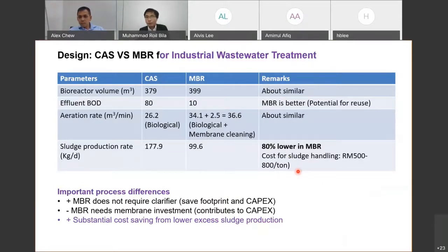So if you have a waste stream that has a very high COD, you have a very good chance for cost saving by upgrading the activated sludge system to membrane bioreactor. Some of the important process differences is that, the same as for the domestic, in MBR we don't need a clarifier, so we can save the footprint and then capex. But we also need capex to buy the membrane, but we will be able to substantially save from reduction in the production of the sludge.